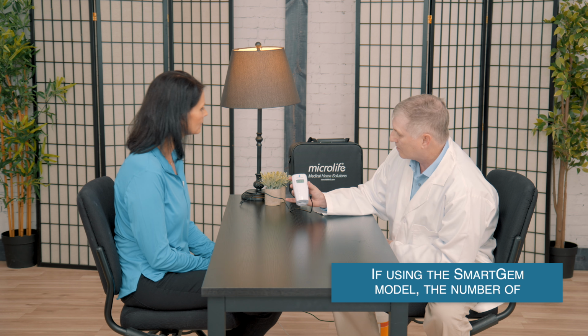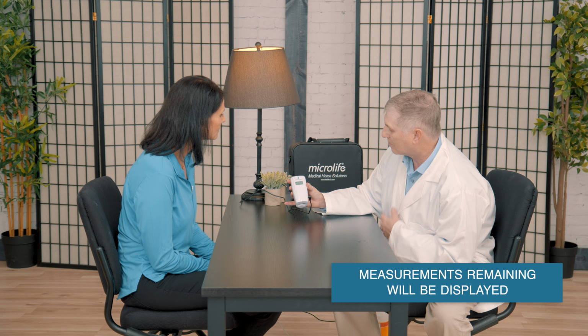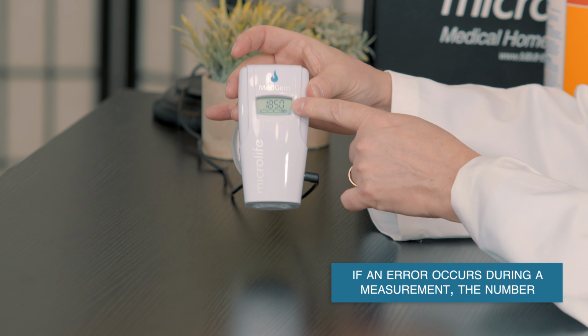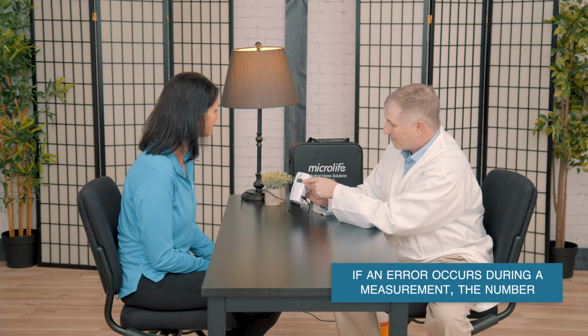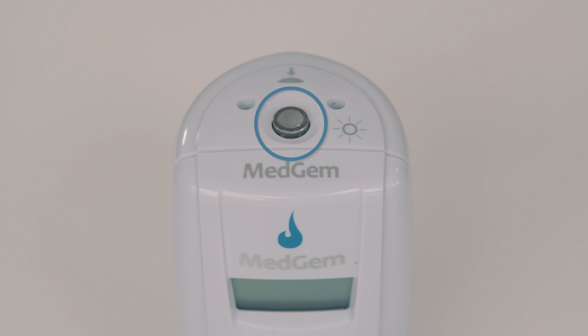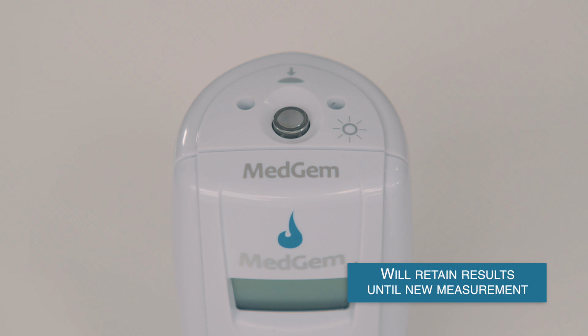You can then review the RMR and VO2 readings directly on the device's display with your patient. These readings will alternate every 2 seconds until the MedGem device is disconnected from the power source or the start button on the top of the MedGem device is pushed. The device will retain measurement results until a new measurement is begun.